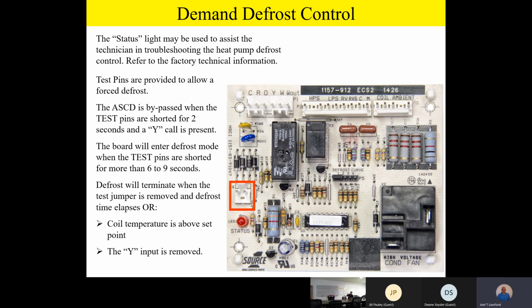If I have a Y call from the thermostat, or a Y call is present, and I jumper those test pins for more than 2 seconds, I bypass the anti-short cycle timer. If I continue to hold that short on those test pins for 6 to 9 seconds, it'll go into a defrost, and it'll stay in defrost until I remove those jumper pins. Now, if I force a defrost, let's say I hold those pins for 10 seconds and it's in a defrost and I remove the jumper, it will then terminate defrost as long as the coil temperature reaches the 55-degree termination point.